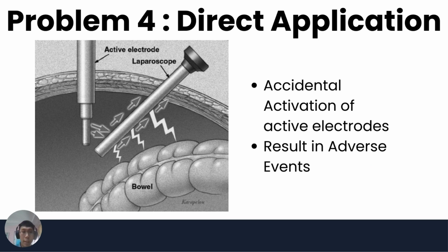The fourth problem is direct application. Accidentally activating an electrosurgical unit is unfortunately quite common. Many of these units operate using pedals, which can easily be triggered by a surgical team member leaning on them or by placing a heavy surgical instrument on top. It is important to note that having one team member manipulate the electrosurgical instrument while another activates the unit carries significant risks and could lead to adverse events. If someone unintentionally activates the ESU, they could potentially cause harm by applying the electrode to the wrong site or anatomical area of the patient, or inadvertently shorting to another conductive material.